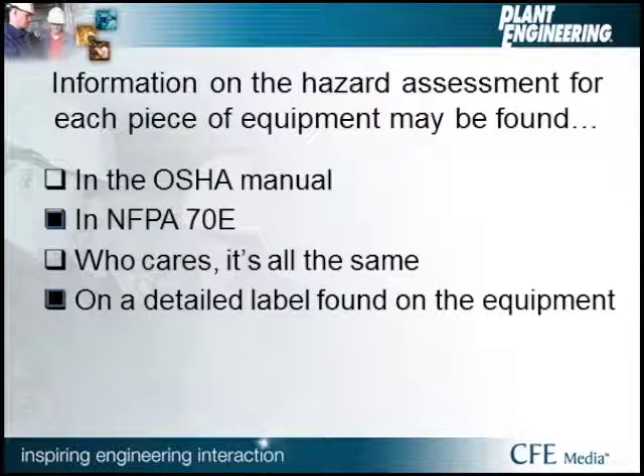Information on hazard assessment for each piece of equipment can be found in NFPA 70E or on a detailed label found on the equipment. Now, NFPA 70E says that we have to review those assessments at least every 5 years unless there's been changes in the equipment or the process, which would mean we do it more often.